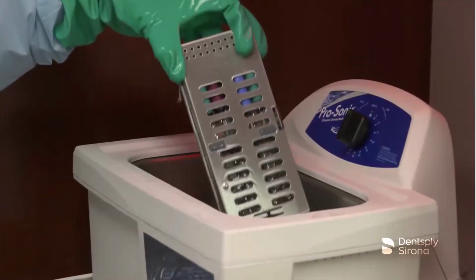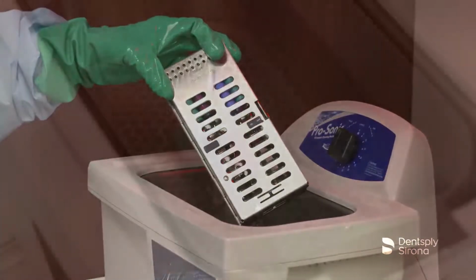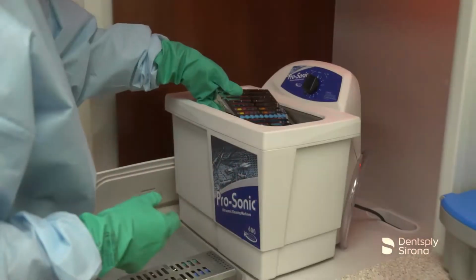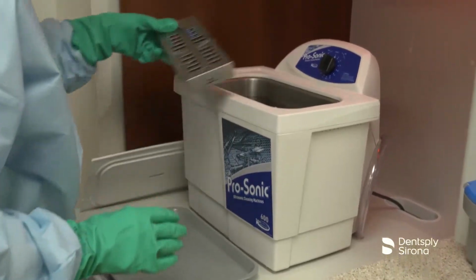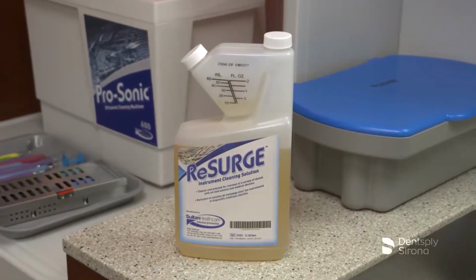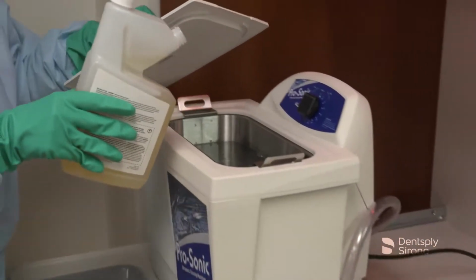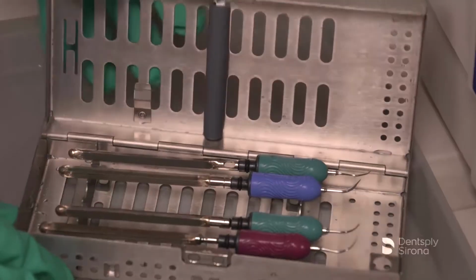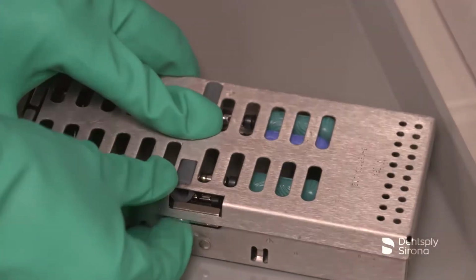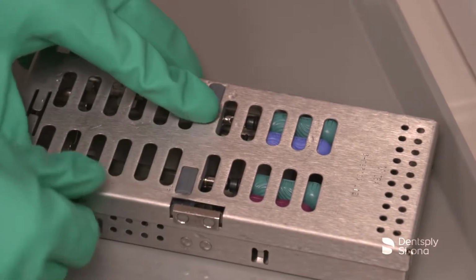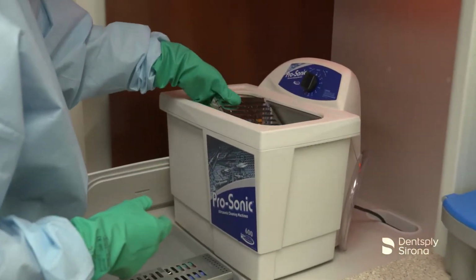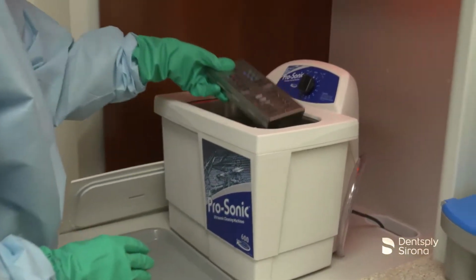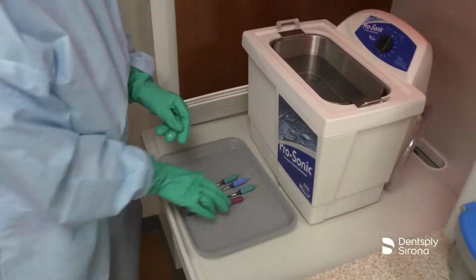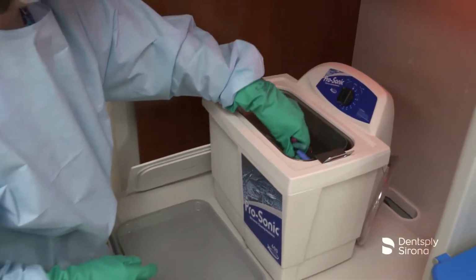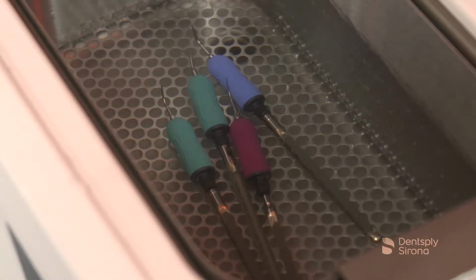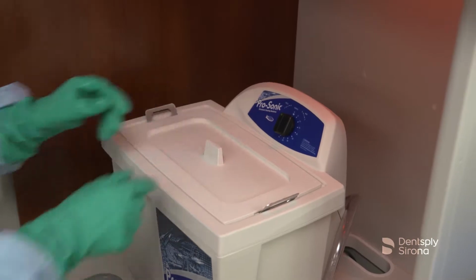Automated cleaners increase the efficiency of the cleaning process and reduce the handling of sharp instruments. It is important to follow manufacturer's instructions for instrument cleaning solutions, carefully observing the concentration rates and contact times. A pH-neutral instrument cleaning solution, such as Resurge, may be used for up to 15 minutes in an ultrasonic bath. When placing Cavitron inserts into an ultrasonic bath, the use of an instrument cassette is recommended to reduce the risk of insert damage. Utilizing a cassette for all instruments protects instruments from damage and minimizes the clinician's exposure time to soiled, loose instruments. If cassettes are not an option, place the instruments into a basket. Cavitron inserts should be placed in the ultrasonic bath basket separate from all other instruments to protect them from potential damage.